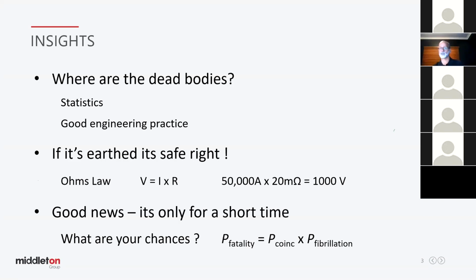So what are your chances of survival? Well, the probability of fatality is seen as being equal to the probability of coincidence times the probability of fibrillation. So breaking coincidence down a little bit, and we'll see this a little bit later, is: what's the likelihood that you or a person might be in contact with a particular metallic or conductive item during an earth fault? It's going to create a voltage on that item.